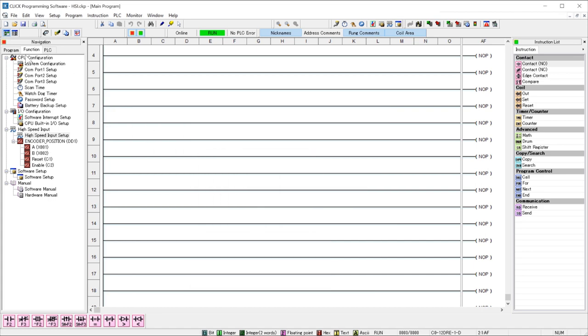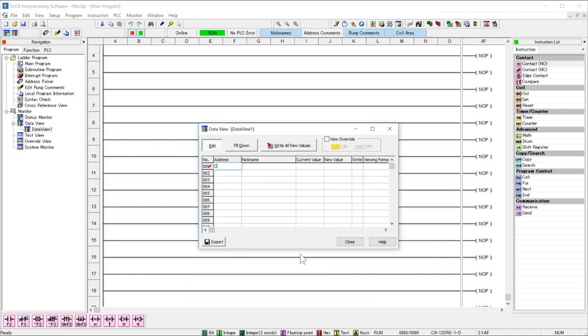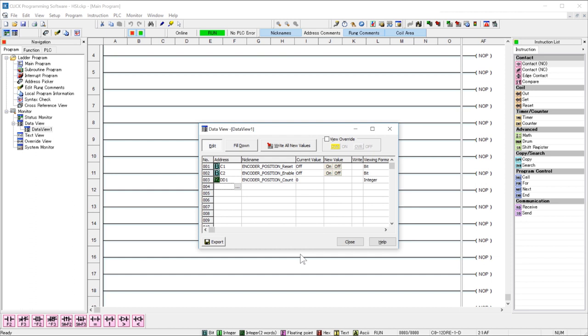So we will need to open up the data view. I am going to add my reset bit, my enable bit, and then my count. Now I am going to enable the count by double clicking here and then spin the encoder. You should see the pulses at this point.